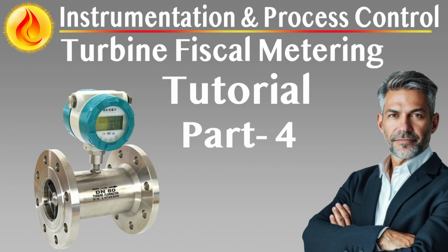Typically, 5 consecutive runs must fall within a total spread of less than 0.05% to be considered valid. If proving results deviate beyond this threshold, the system must continue up to 10 runs before aborting the sequence and raising an alarm. Failed runs must be logged, annotated, and retained for audit purposes, even if they are excluded from the final calibration outcome.